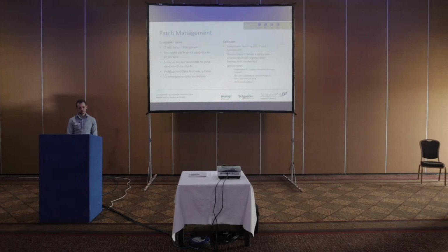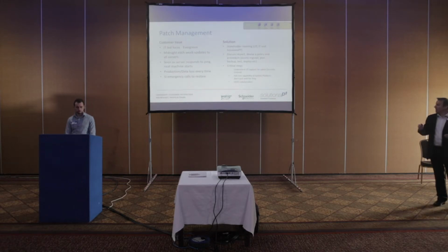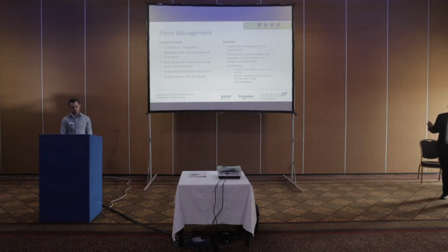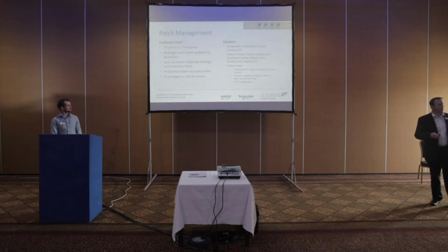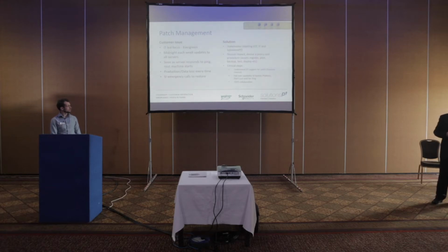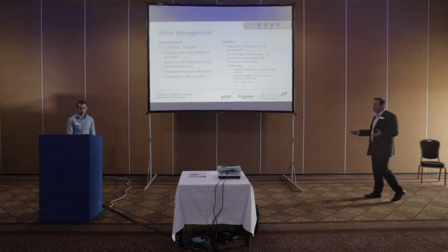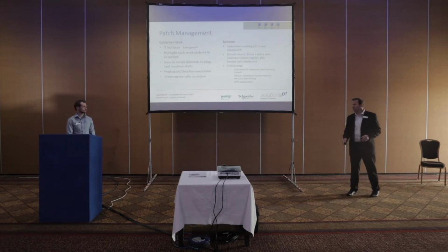We also highlighted, as a team, that the critical step was for everyone to understand the support for the patch management. Obviously for OT to realize just how important it is to patch your systems. And also that the IT understands that there's certain failover capabilities of System Platform. The servers need to be restored and running for a certain amount of time so that synchronization can take place before you take down the other server. And again, it just highlights the need for the OT and IT collaboration.